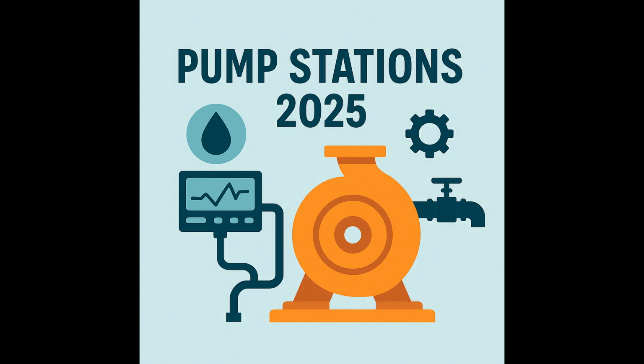The green zone, I like that analogy. So where does the allowable operating region fit in that? Is that like the yellow zone? Exactly. The allowable operating region, AOR, is a broader range. The pump can still run here without causing unacceptable damage, but efficiency definitely drops and the risk of wear increases. So it's acceptable but not ideal, your yellow zone. Got it. The best practice, the goal, is to keep pumps in the POR as much as possible, only allowing temporary operation in the AOR during, say, fluctuating flows or maybe emergencies. So we really want to keep them in that green zone.